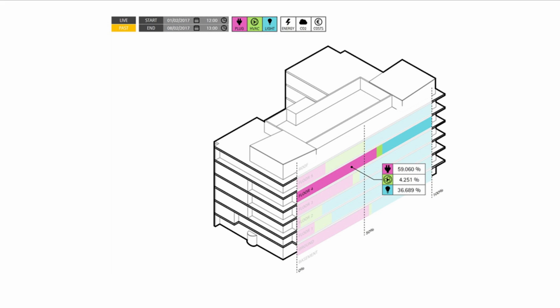But this is an example of one I did in 2016 at a building called The Dock in Dublin, where we were effectively taking the building management system in the basement, which I think is a glorified alarm clock because it's got some times and some temperatures and it goes off if there's a problem, and adding actual engineering calculations and insight across the entire system, not just at the machine level, in order to work out things that you can do to save energy across the building, be that correcting things such as simultaneous heating and cooling, mixing outdoor air temperature, where the biggest issues are with set point variance, or even some cultural stuff.